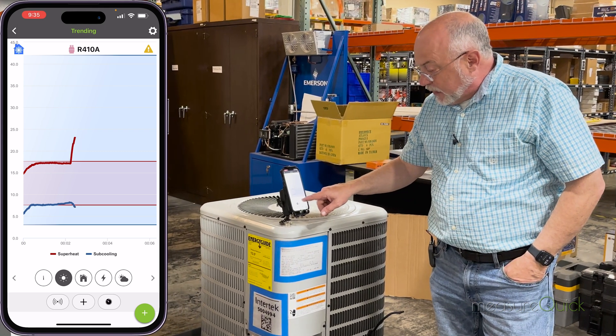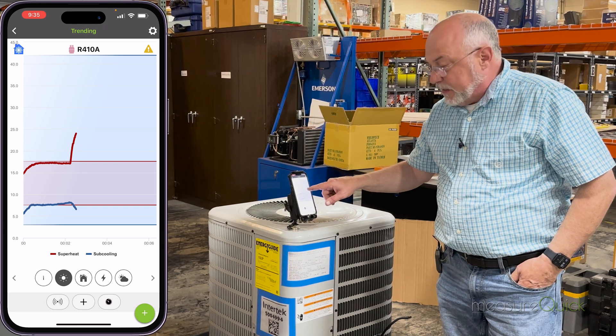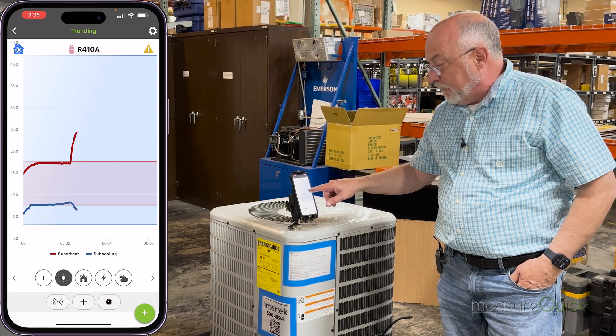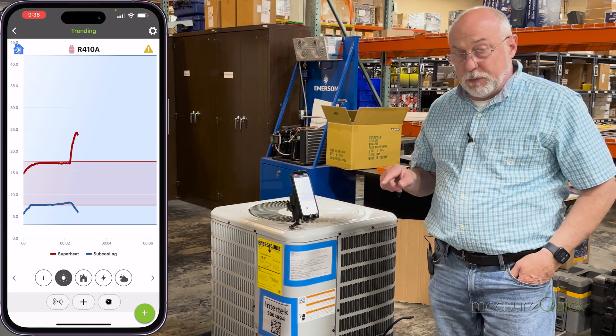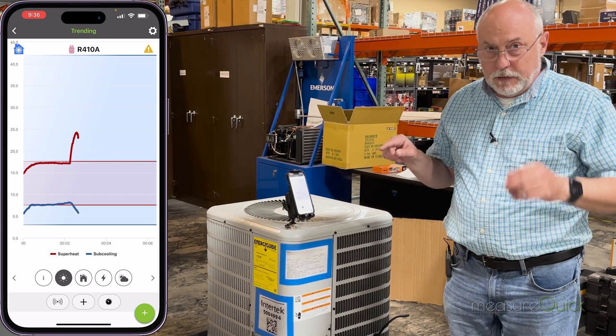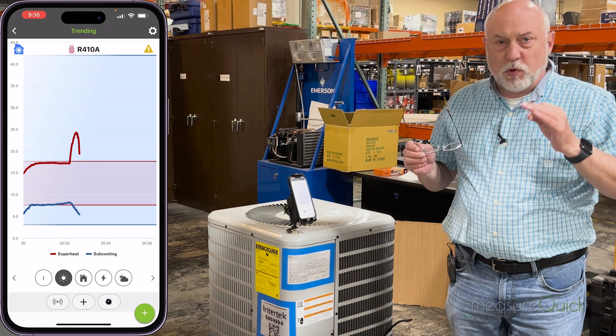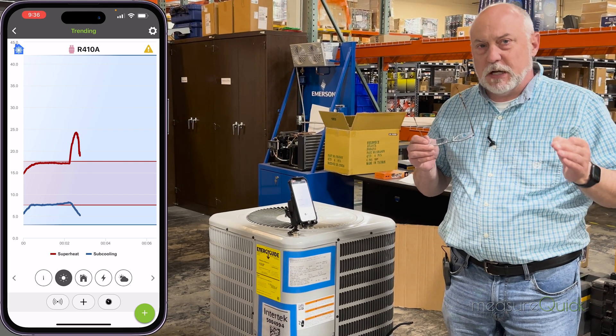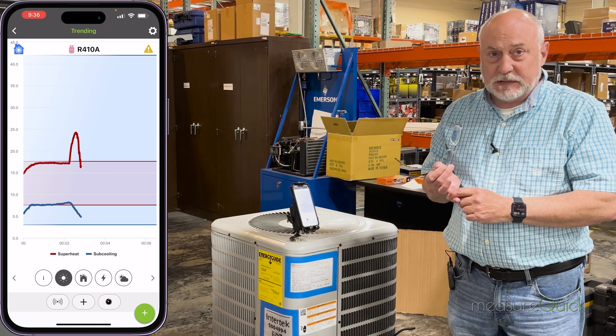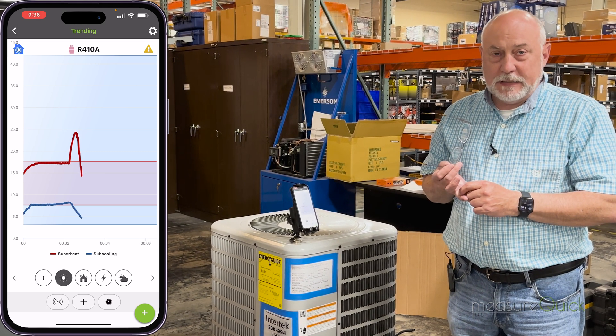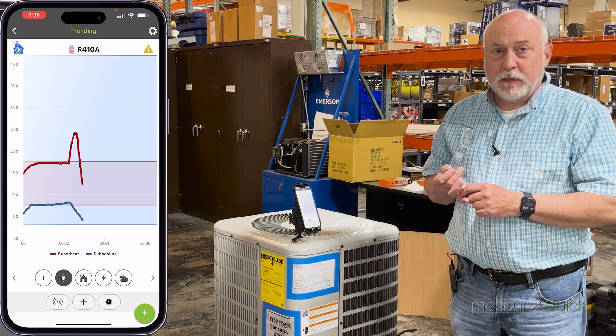Now let's take a look at our trends. This is a trend of superheat and subcooling. The red line is the superheat. You can see right away the superheat is shooting way up and our subcooling is starting to trend down, and our superheat is now coming back down again. So why is this happening?